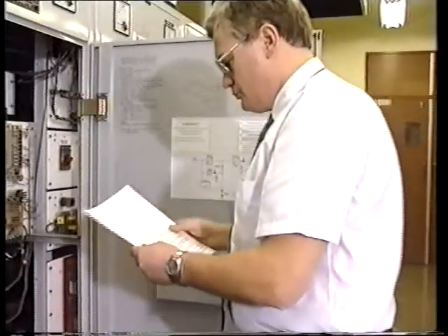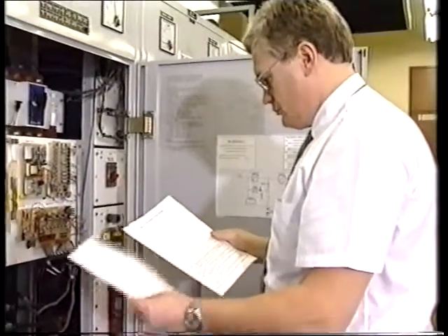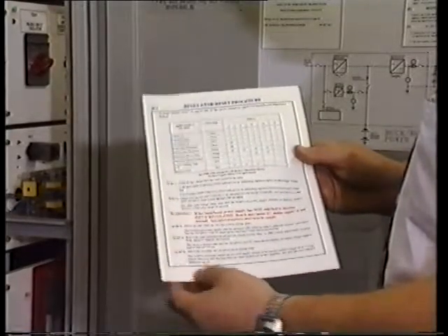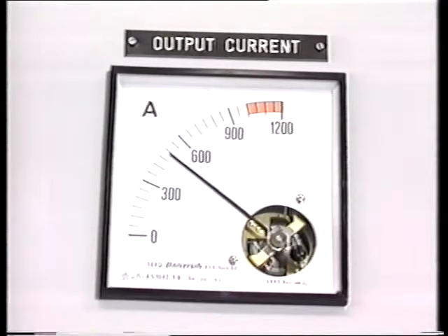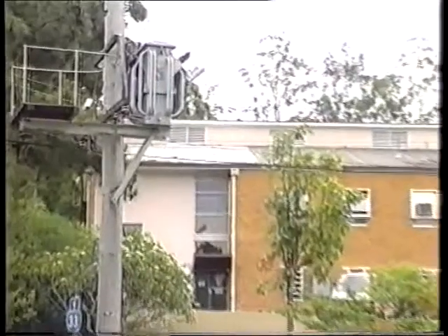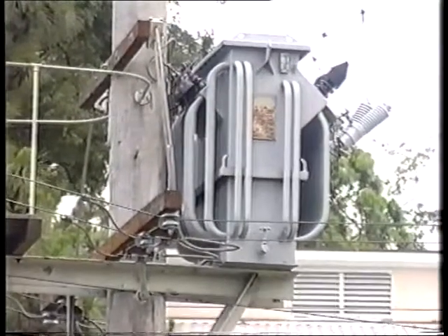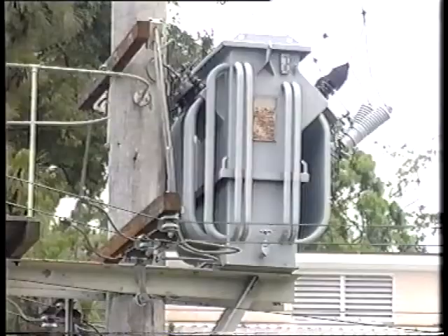Now to C, the regulator reset procedure, which is carried out if the buck-boost inverter has failed. The buck-boost regulator will continue to supply output current in the unregulated mode until the inverter is reset. A large mains surge, or sag, is one of the most common causes of buck-boost output regulation failure.